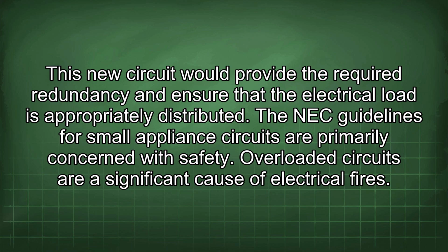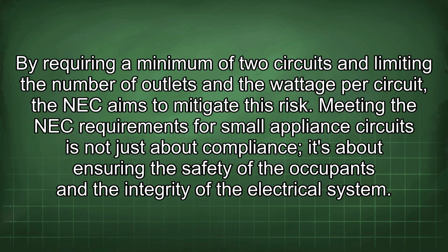The NEC guidelines for small appliance circuits are primarily concerned with safety. Overloaded circuits are a significant cause of electrical fires. By requiring a minimum of 2 circuits and limiting the number of outlets and the wattage per circuit, the NEC aims to mitigate this risk. Meeting the NEC requirements for small appliance circuits is not just about compliance, it's about ensuring the safety of the occupants and the integrity of the electrical system.